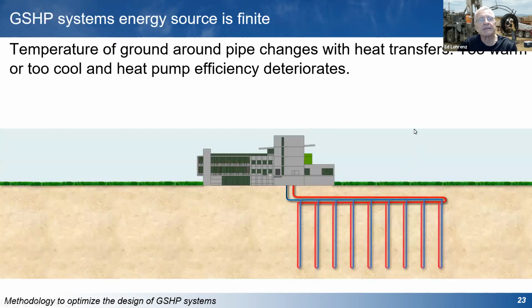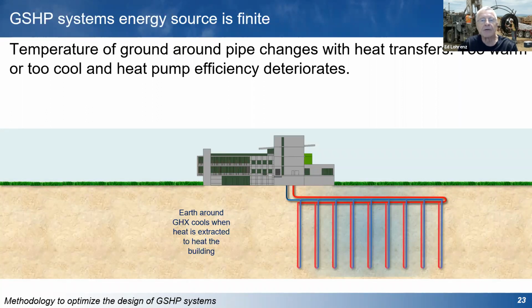A ground source system is fundamentally different. What happens with a ground source system is you're basically working with a storage system. When you're taking heat from the ground to heat the building, you're cooling off the ground. When you're taking heat out of the building, when you're cooling the building, you're warming up the ground. So it can get too warm, it can get too cold if that ground heat exchanger isn't big enough. And then the system suffers with inefficient operation of the heat pumps. And in some cases, I've seen systems like that fail where the ground temperature just gets too warm for the system to operate efficiently.